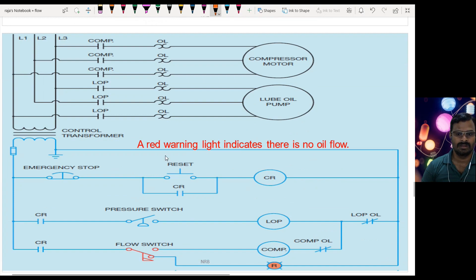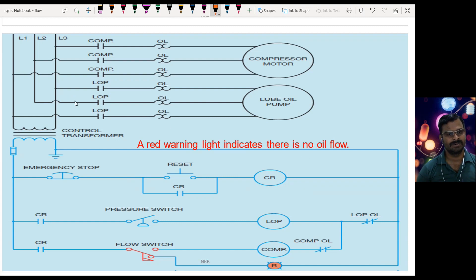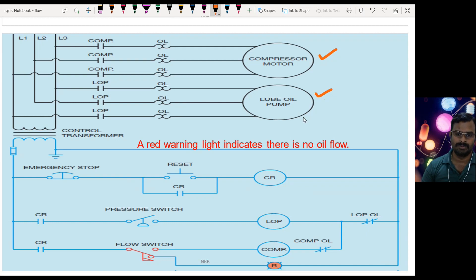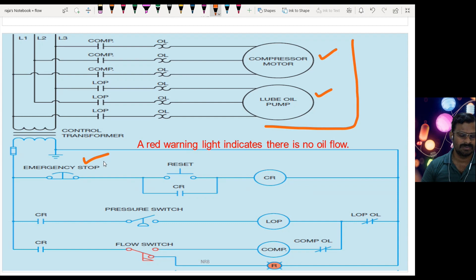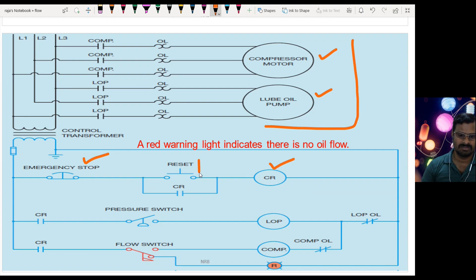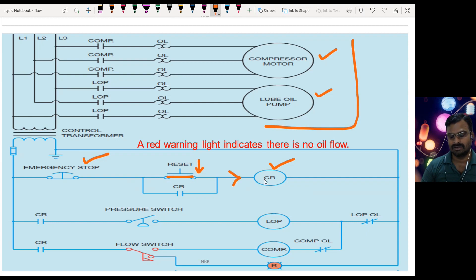Now let us see the control wiring diagram. We have two motors — one is a compressor motor and the other is a lube oil pump motor. The upper part is the power circuit and the lower is the control circuit. In the control circuit we have an emergency stop switch, a reset or on switch, and a control relay. By pressing the reset button, the contact closes and current flows to the control relay coil.